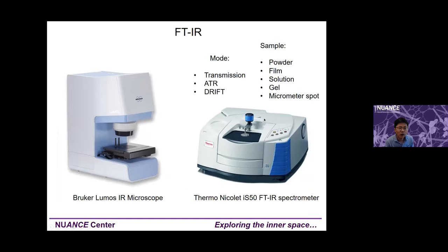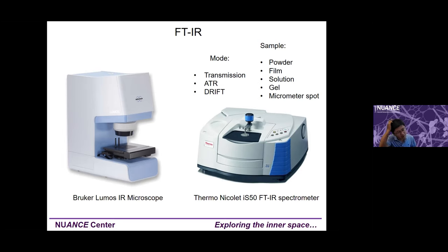Next is FTIR. In our lab we have two FTIRs. The right one is a regular FTIR for basic samples like powder, film, solution, and gel. For micro-spot work — for example if you have a sample with a small area that is different and you want to identify it — we have the left one, the Micro-FTIR, also called micro-FTIR. We can image that area and collect IR from there. Both instruments have ATR mode, which is almost sample-preparation-free. The ATR crystal on the left one is integrated — you just click a button and it comes out.